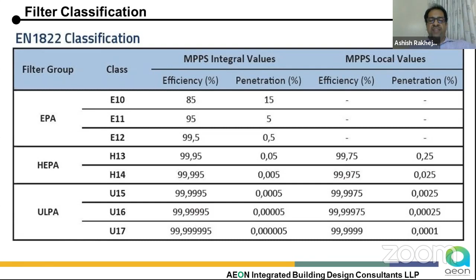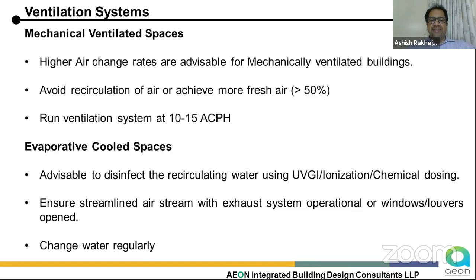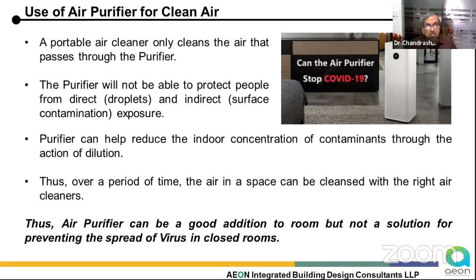The ISHRAE-ASHRAE guidelines also talk about mechanically ventilated spaces and evaporatively cooled spaces and how to handle them. Since these spaces work on 100% fresh air, they are relatively easy to take care of, but again the dust particles in the air remain a challenge. Air purifiers are also being talked about, which can be a good addition to a room since there's a very small air change rate taking place, but they may not be the ideal solution for preventing the spread of virus.